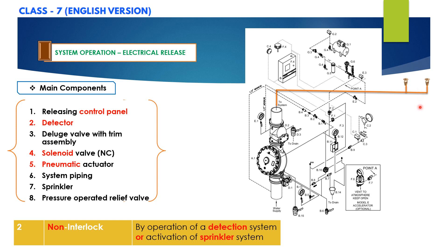However, if a sprinkler opens prior to the operation of the detection devices, or anytime the pneumatic pressure in the sprinkler piping is lost, the pneumatic actuator will open. When the pneumatic actuator opens, pressure is released from the priming chamber faster than it is supplied through the restricted orifice, and the deluge valve clapper opens to allow water to flow into the system piping and alarm devices.